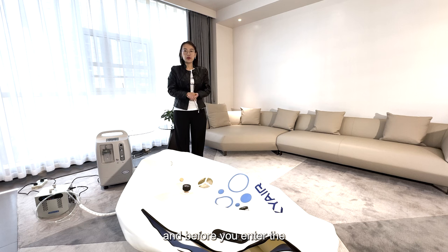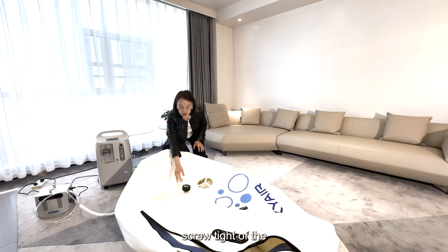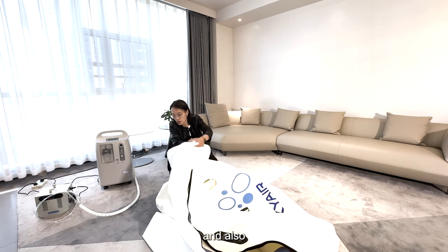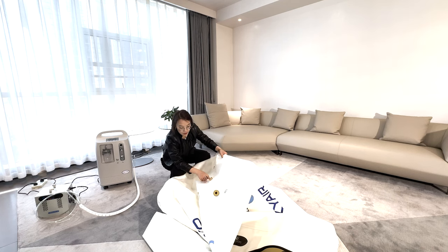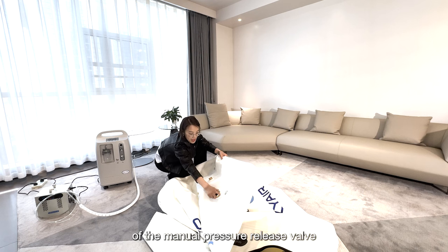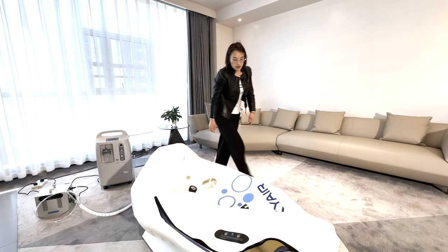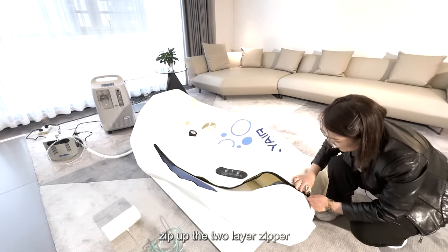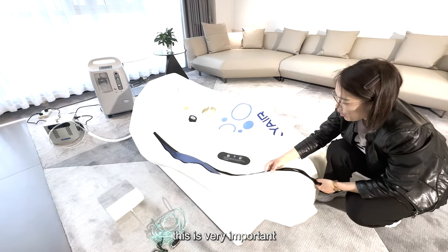Before you enter the single hyperbaric chamber, you must make sure to screw tight the external pressure gauge, screw tight the emergency pressure release valve, and screw tight the manual pressure release valve. And last, you must make sure to zip up the double-layer zipper before you enter the chamber. This is very important.